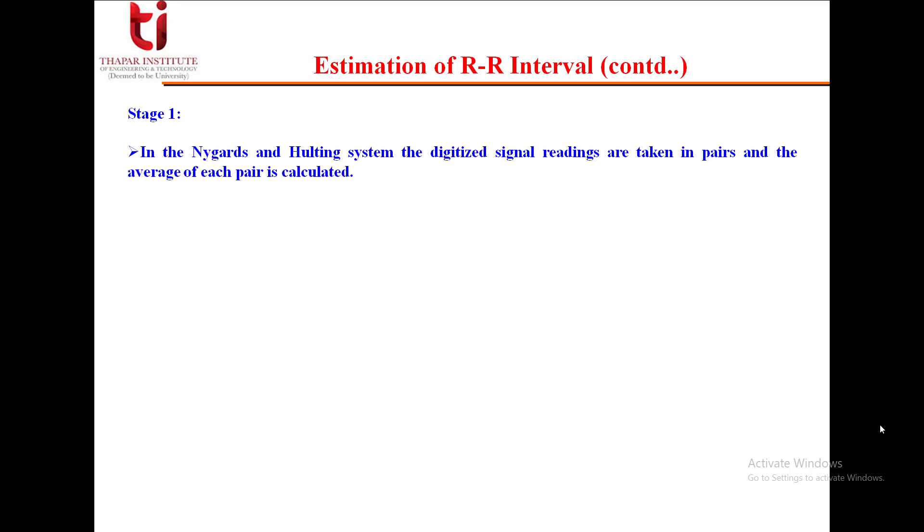In stage 1, in the Nygards and Hulting system, the digitized signal readings are taken in pairs and the average of each pair is calculated. This averaging process reduces the effects of mains fluctuation and voltage spikes from chest muscle activity.